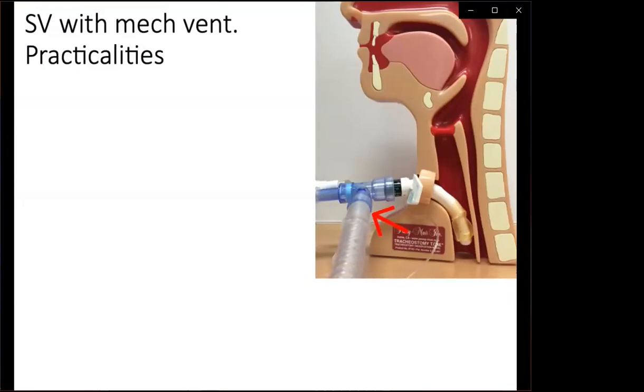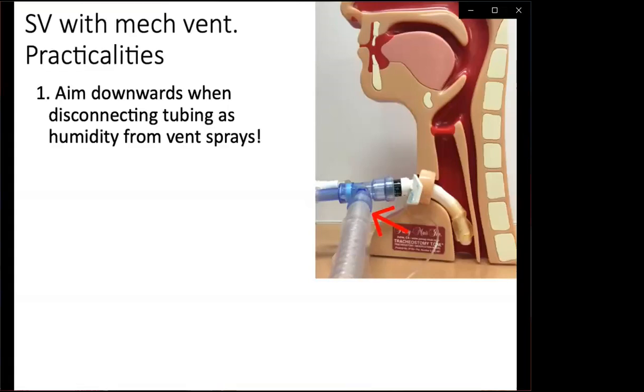And to put the speaking valve in line with the ventilator in the first place, you always need to disconnect the closed ventilator circuit. When you do so, the ventilator circuit always has some secretions inside it. So make sure that you aim the tubing downwards when you disconnect, because you have a nurse or a physio or another speechy colleague standing on the opposite side of you.